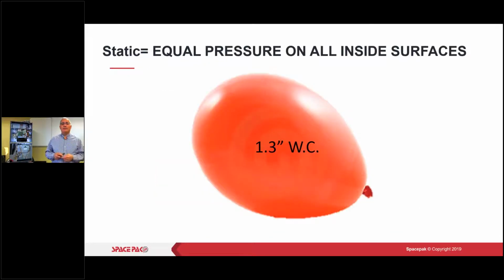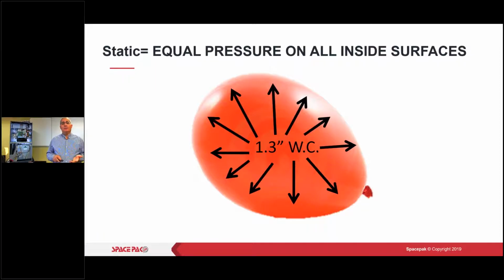So again, there's that balloon scenario. This is what I use when I'm trying to explain to somebody what a SpacePak system is. I pressurize this balloon, I poke holes in it, but it doesn't pop. I get equal flow coming out of all the holes, all right? And that's what we do with our system. So the plenum has to be pressurized. So it's very important that we have no leaks in our plenum. We run our plenum properly. Our drops coming off our plenum are spaced properly, and we have our tubing coming off properly. We don't have any crazy bends or anything like that, which can create leaks, which can create noise and problems.